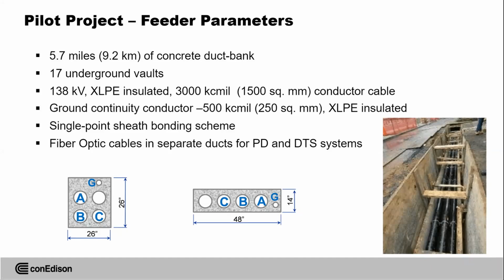So we decided we need a cable monitoring system. The first question that came was, okay, what project will we use as a pilot? On your screen right now, you see the project which was chosen in 2016 as a pilot. It's 5.7 miles, 9.2 kilometers of concrete duct bank, single circuit, underground, operating voltage 138 kV, XLPE insulated, 3000 kcmil conductor, which is 1500 square millimeters. The ground continuity conductor is 500 kcmil, also XLPE insulated, with a single point bonding scheme. We also use fiber optic cable in a separate duct for partial discharge and DTS system. That was and still is our standard. And that project was chosen as a pilot for installation of the new cable monitoring system.